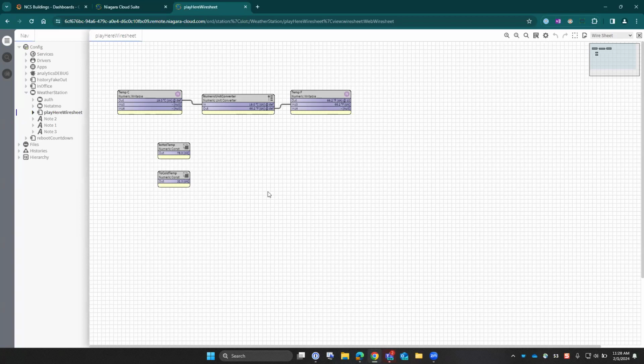And I would have to wait until I went home because I don't have any port forwarding. I don't have any VPN access to that Jace. It is isolated on that network. Here I can now log in and actually do Wiresheet changes and logic to update whatever I put in place. Say I recommission, and a customer complains that I need to balance this VAV series a little better, right? I can now not go to that location. I can remote in and do that logic.